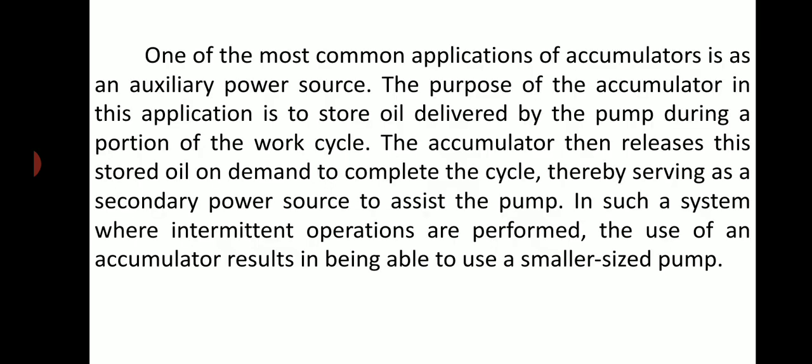One of the most common applications of accumulators is as an auxiliary power source. The purpose of the accumulator in this application is to store oil delivered by the pump during a portion of the work cycle. The accumulator then releases this stored oil on demand to complete the cycle, thereby serving as a secondary power source to assist the pump.